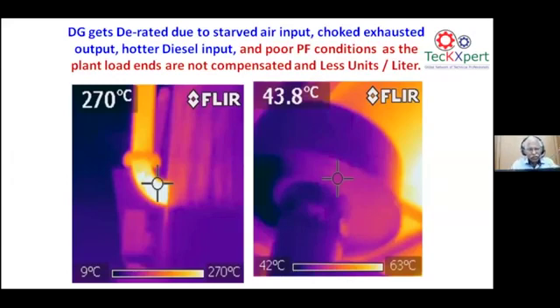So a generator's capacity can be restored if the diesel input is maintained at 38 degrees, where the centistokes, or the viscosity value, of the diesel is excellent. First point. Second point is that there is no back pressure in the genset. And the third point is the poor PF conditions in the load, which are corrected with load compensation. Definitely the generator capacity can be enhanced by 10 to 20% by all these factors.